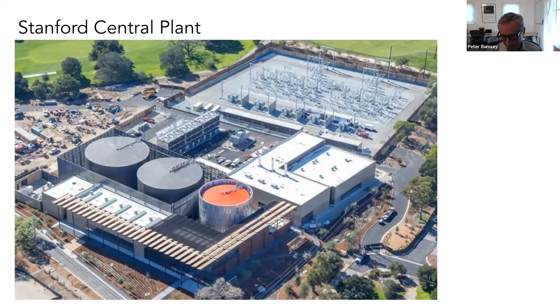So one way they do it is in the afternoons, they might be in cooling and they're making lots of chilled water, sending it out to the building. So the waste product is heat. So they'll put it in the tank so that the next morning, when it's a cool morning, they can use that heat that was generated the afternoon before. In that climate, they get a lot of warm, not hot, but warm days in the afternoon and cool mornings.